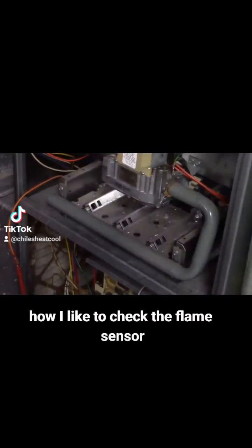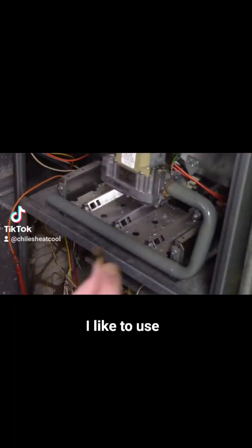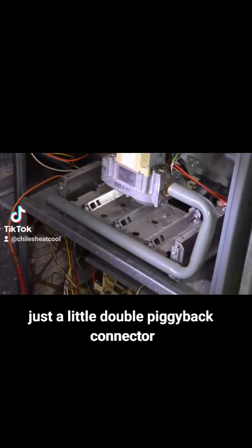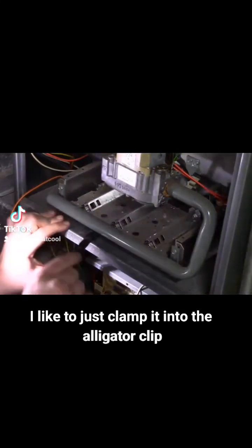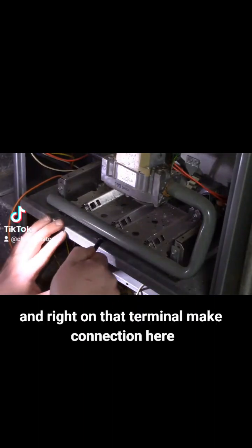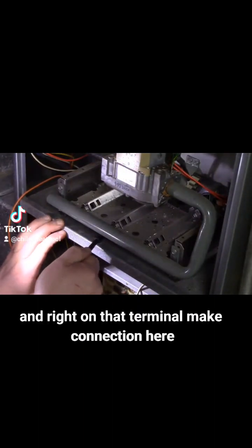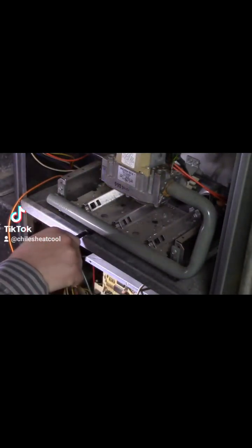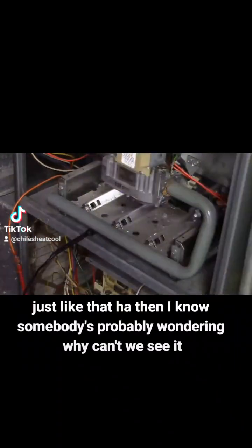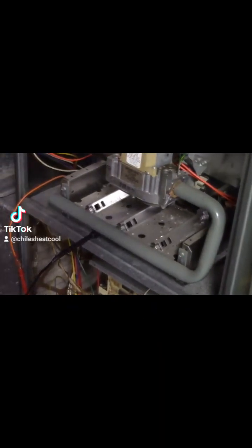Now I'm going to do my normal way how I like to check the flame sensor. I like to use this. It's just a little double piggyback connector. I like to just clamp it into the alligator clip, pull it down like this, and right on that terminal make a connection here. Just like that. Then I know somebody's probably going, why can't we see it? Well, we will. We'll create a little earthquake camera action. Right? Earthquake, yes, I know. And you can see kinda how it's connected right there. Just like that on the flame sensor.